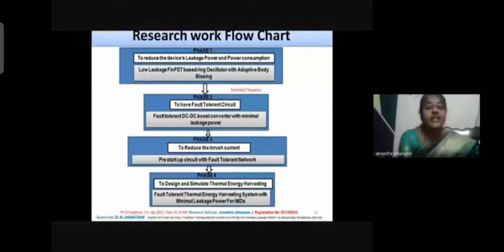In the second phase, we focused on the fault tolerant circuit, boosting the voltage from the thermoelectric generator to the level required by the IMDs. We designed a fault tolerant DC to DC boost converter with minimal leakage power.